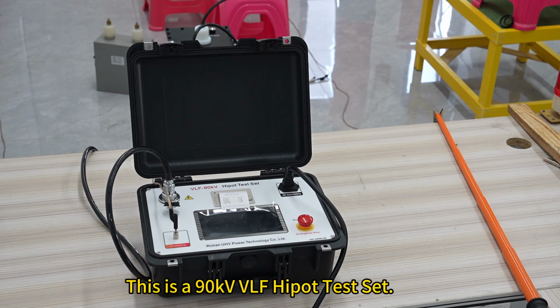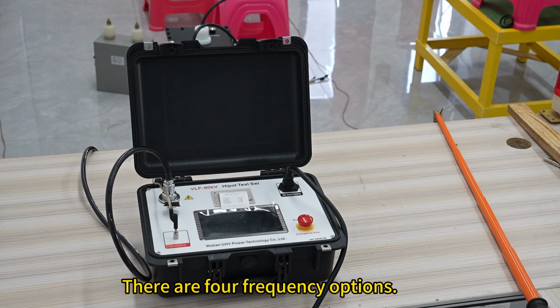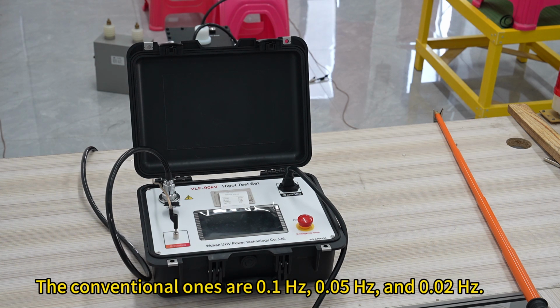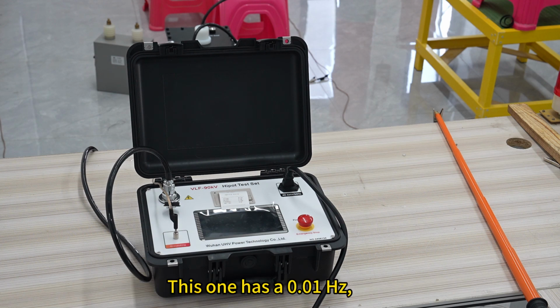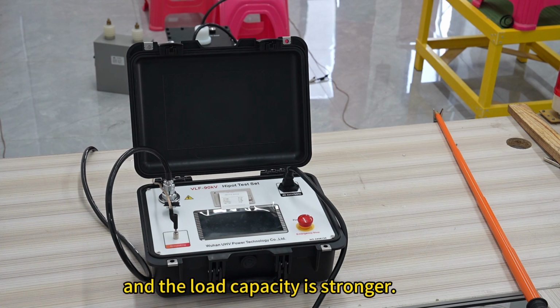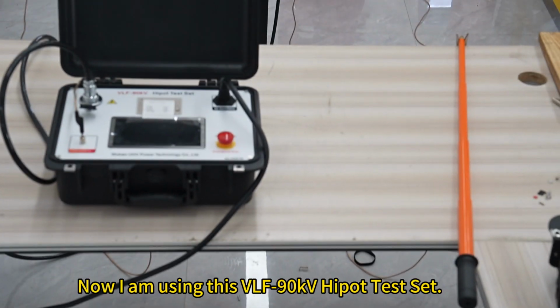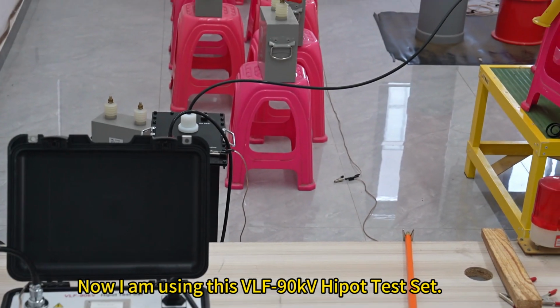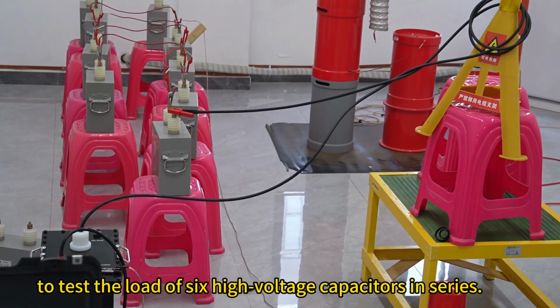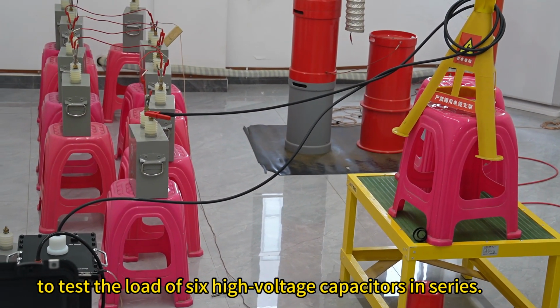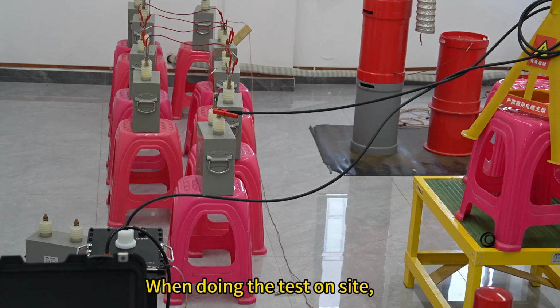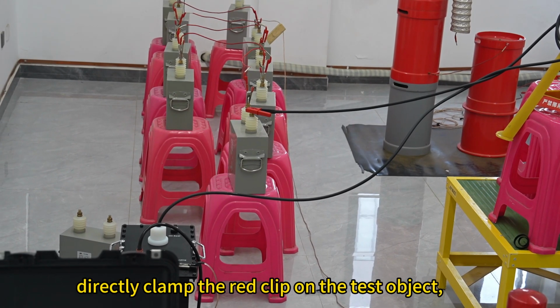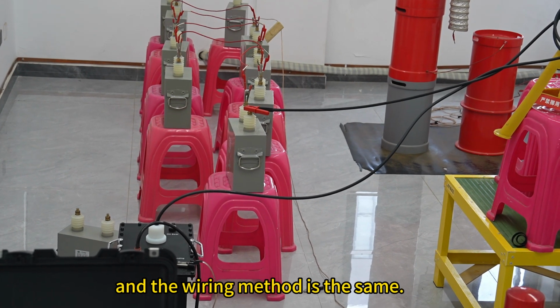This is a 90 kV VLF Hipot test set. There are 4 frequency options. The conventional ones are 0.1 Hz, 0.05 Hz, and 0.02 Hz. This one has a 0.01 Hz, and the load capacity is stronger. Now I am using this VLF-90KV Hipot test set to test the load of 6 high-voltage capacitors in series. When doing the test on site, directly clamp the red clip on the test object, and the wiring method is the same.